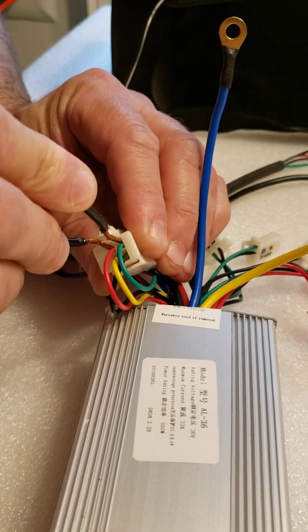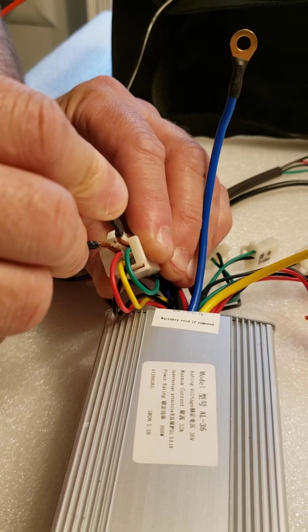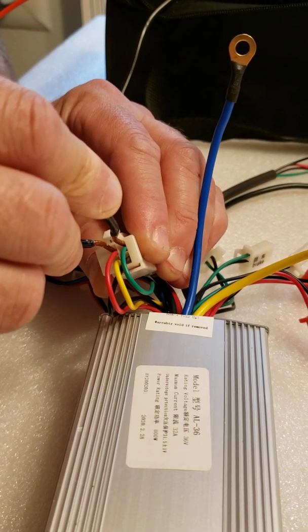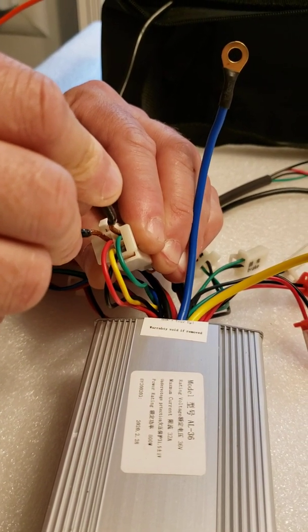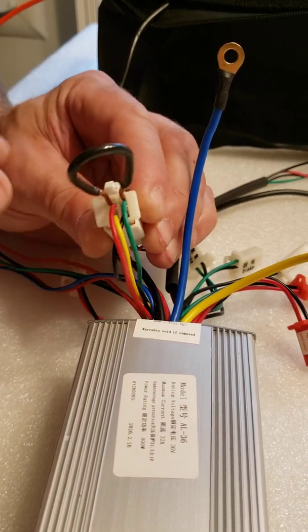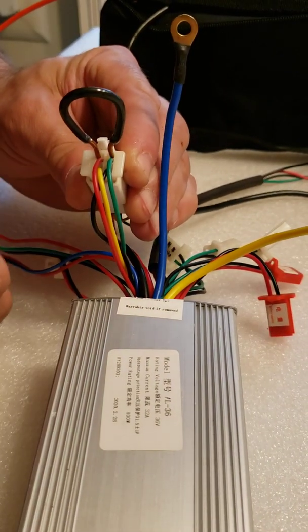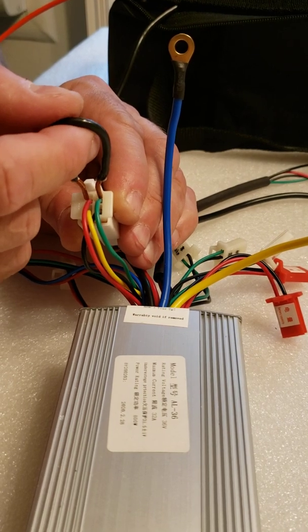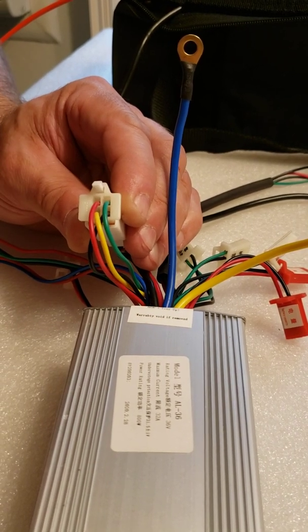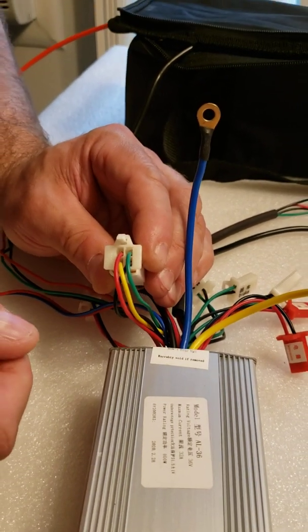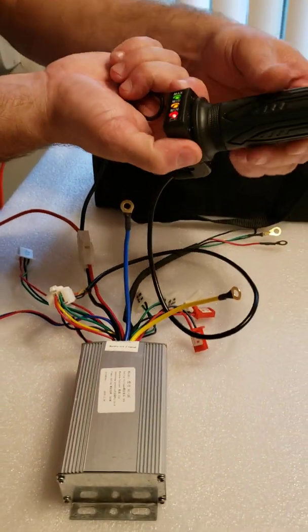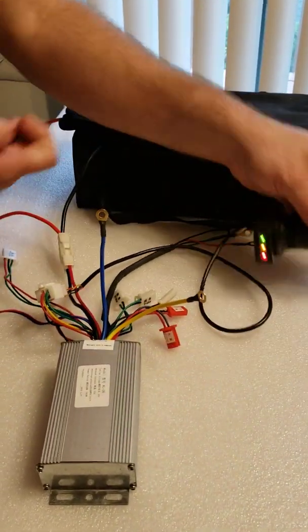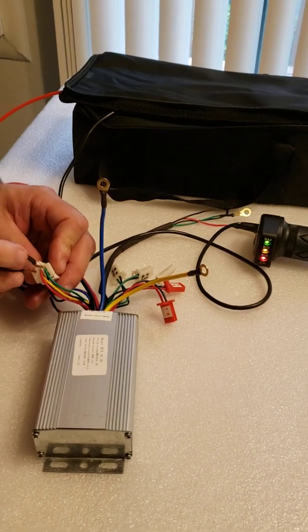This will override your handle. What that means: if you short those two wires like I just showed you—the green and the red wire—and if your wheels spin in any direction, forward or reverse, it doesn't matter, that means your handle is not sending any signal.